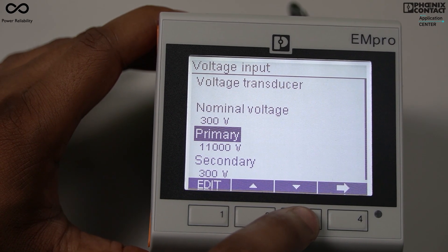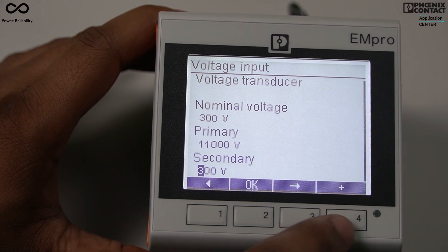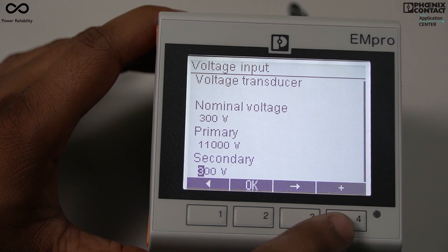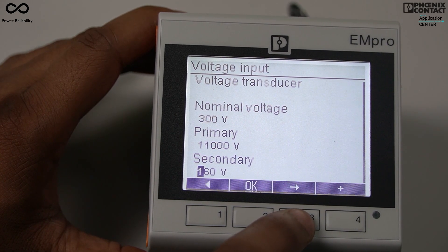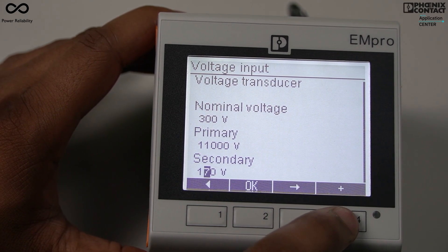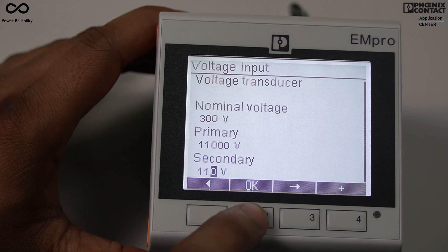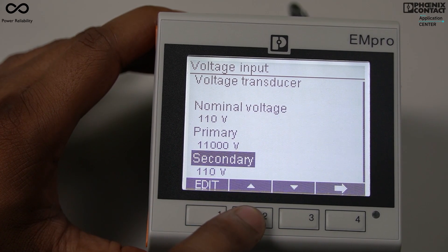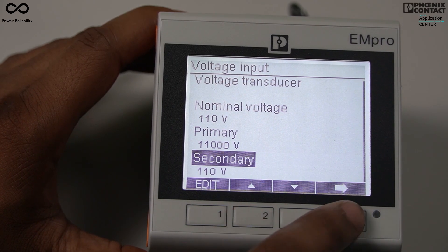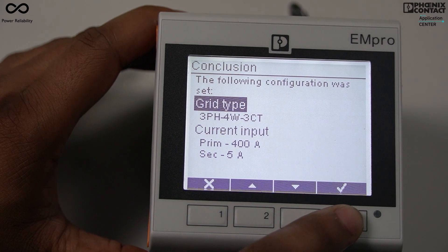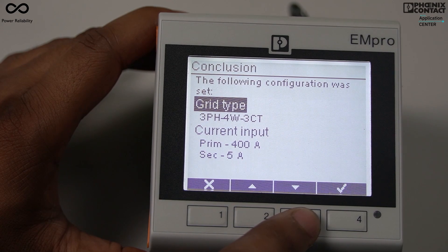Now I need to change the secondary to 110 volt. I will move to secondary and press the edit key, then change the digits to program 110. I press OK. So I have programmed the PT ratio as 11,000 volt / 110 volt. The screen now shows the configuration summary: grid type is three-phase, four-wire, three current transformer; current input is 400/5 ampere.